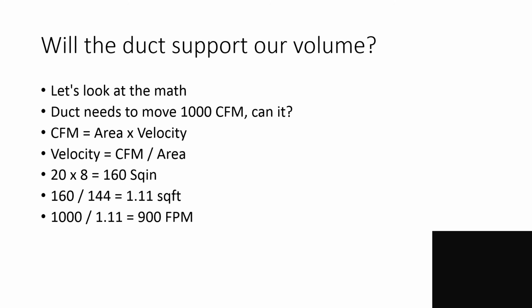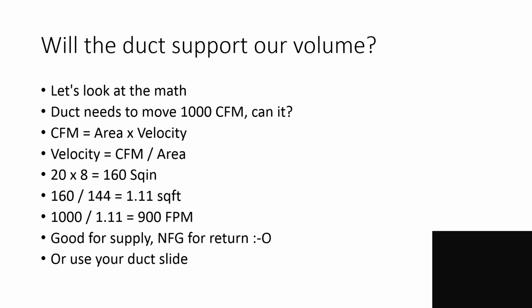Gives me 900 feet per minute. So that would be good for a supply trunk with galvanized metal. It would not be good for a return trunk for galvanized metal. Manual D has in it, or at least the ductulators that I use in my duct design class show, 1,000 feet per minute being a max for metal for your velocity on the supply, and 800 feet per minute being your max for your velocity on the return. So at 900 feet per minute, it's no bueno for the return, but it is okay for the supply.